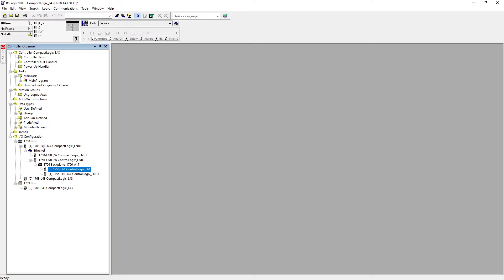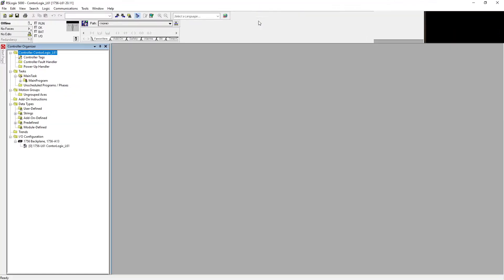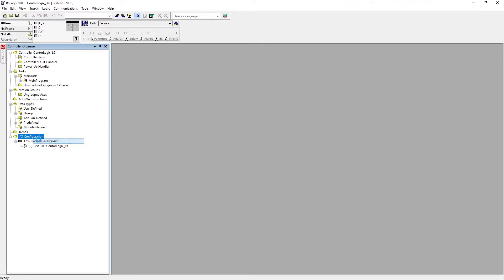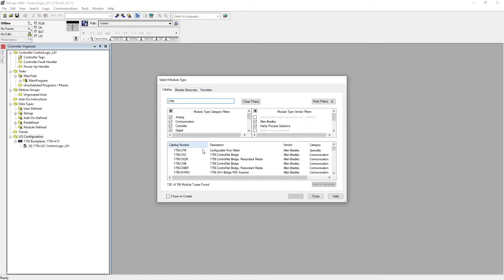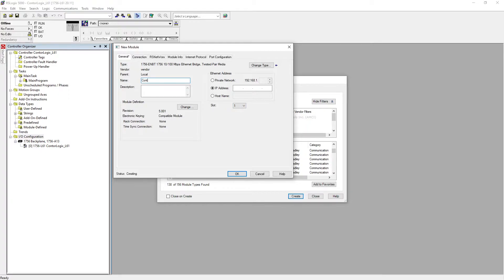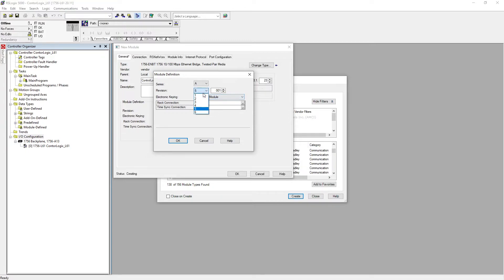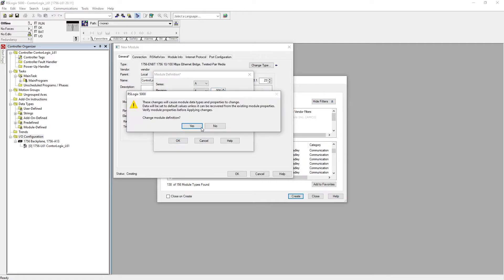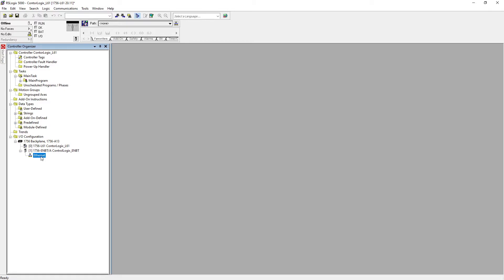OK, so on the compact side — what we did is we added our ENBT card, our Ethernet card for the CompactLogix, and that's going to communicate to the 1756 ControlLogix Ethernet card and then to the processor. Now we need to select our control logic side. Over here we're going to select new module — we're going to select our ControlLogix 1756-ENBT card. Hit create — that's at slot number 1, that's correct. It's going to be 'ControlLogix ENBT,' private network at .23, revision 4.8 — hit OK.